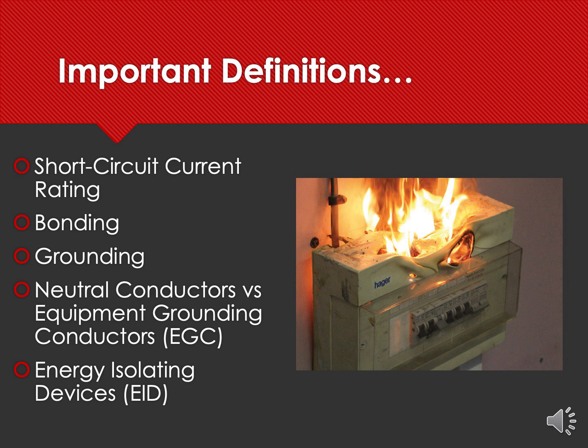Bonding and grounding we'll discuss together in the sense that the purpose of bonding is to equalize voltage between conductive parts on the frame of a piece of equipment, in this case the covers for the panel itself. So we bond things together to equalize voltage so we couldn't touch two different surfaces and have a voltage between them. Grounding then is we take that same bonding connection and connect it to planet Earth in the vicinity of the work location. So the purpose of bonding is to equalize voltage. The purpose of grounding is to put the panel at ground potential in the vicinity of the work location.